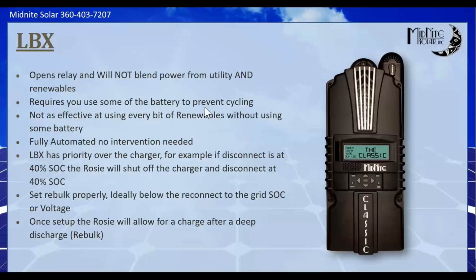Otherwise, you're buying power to recharge the battery every time it reconnects. It does require you to use some of the battery to prevent cycling, whereas in grid support, you could set it for 100% state of charge, and it would physically never let the battery go below 100%. It would always blend the power and fall back over to the grid. In LBX, you really can't do that. You need some delta between the disconnect and the connect. Otherwise, the relay would just sit there click-clack all day long and you wear the relay out. I believe we actually force you into, I think, 5% state of charge between the two as a minimum.